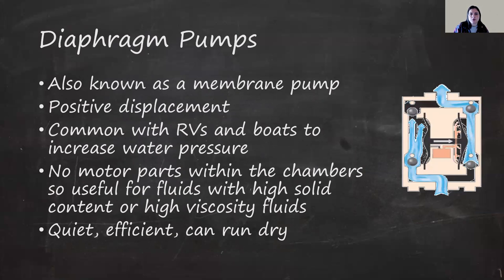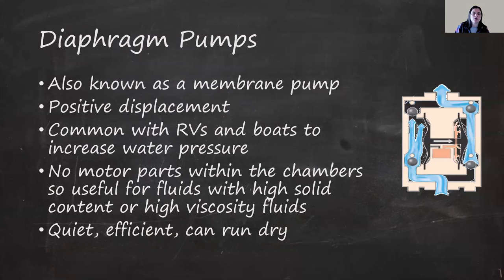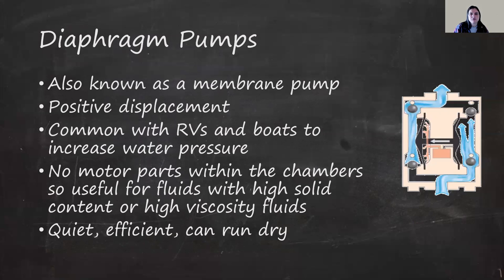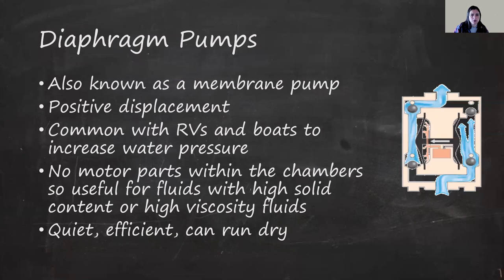Diaphragm pumps are also known as membrane pumps or another type of positive displacement pump. A reciprocating rod moves a flexible diaphragm within a cavity. The volume of the cavity is increased by the diaphragm moving outward. Pressure decreases and water moves into the chamber. Conversely, when the diaphragm moves inward, reducing the size of the cavity, water is forced out. These pumps are often seen in RVs and boats for providing steady flow or increasing water pressure from storage tanks. Fluid is retained within the chamber and, like the peristaltic pump, does not come in contact with the motor. Subsequently, they are capable of handling abrasive or high viscosity fluids and those with high solids content. They are usually quiet, efficient, and capable of running dry.